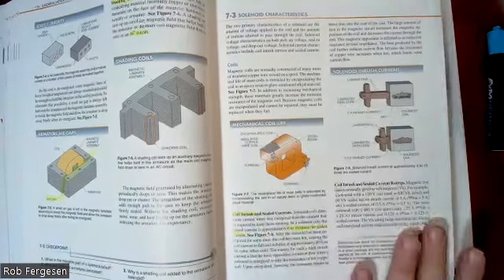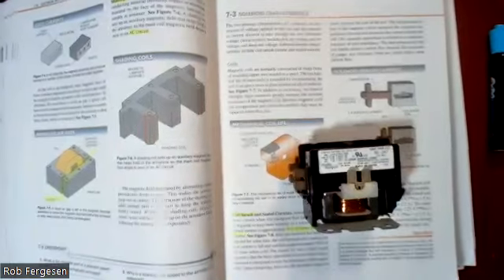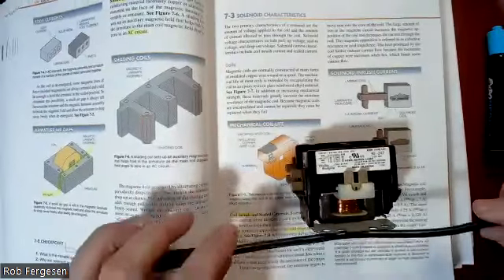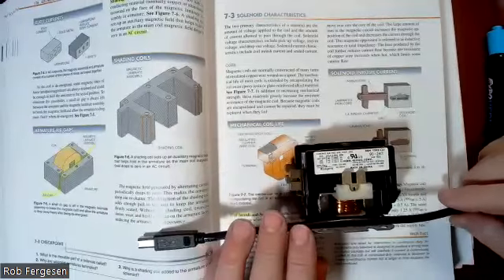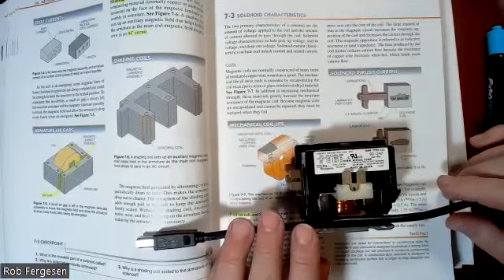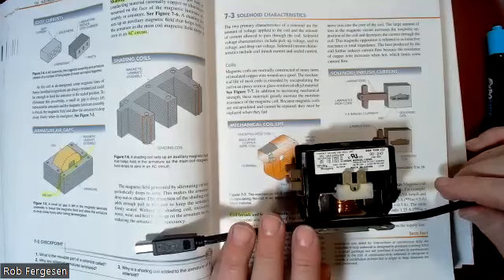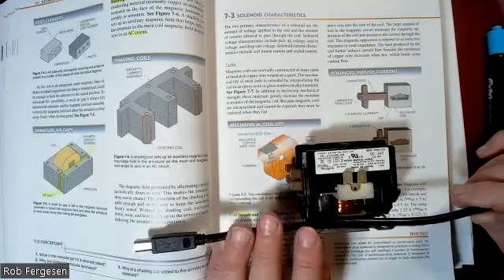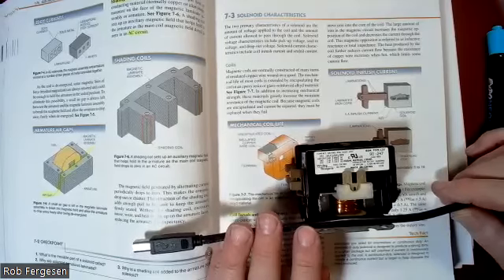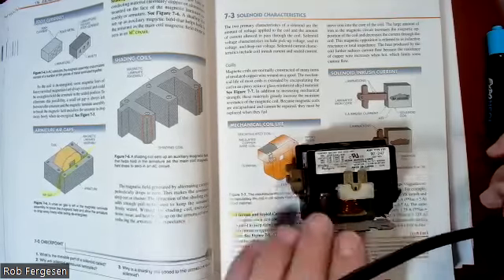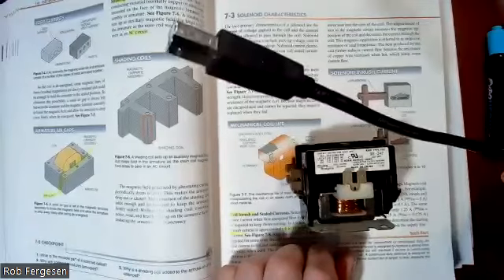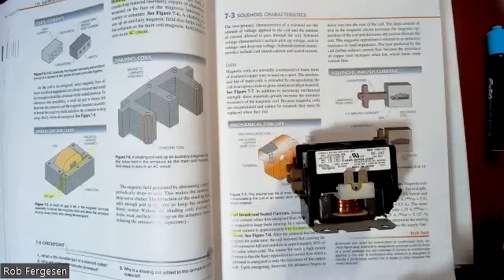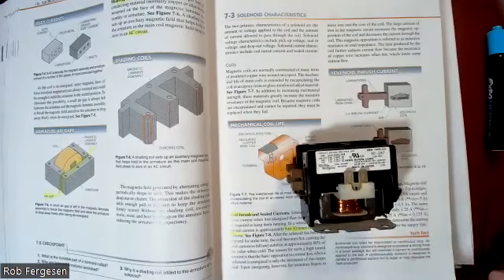If you have one of these big coils, and let's say you run a communication cable nearby to that coil, this is a USB cable, but it could be a communication cable or a cable associated with a sensor. If you run this coil right near this cable, guess what happens every time this contactor turns on? This particular cable will receive a big burst of EMF based on that inrush current.